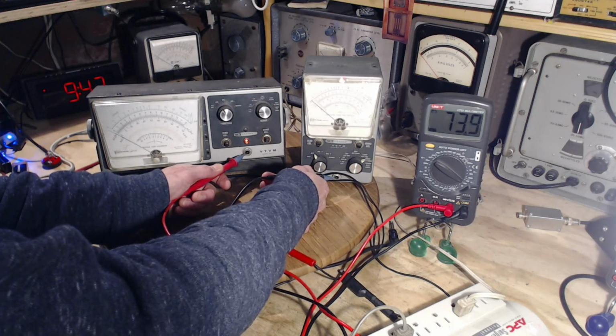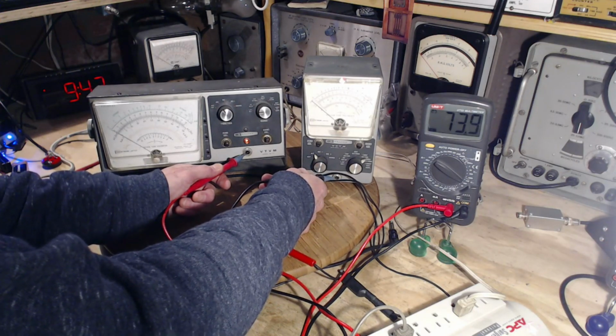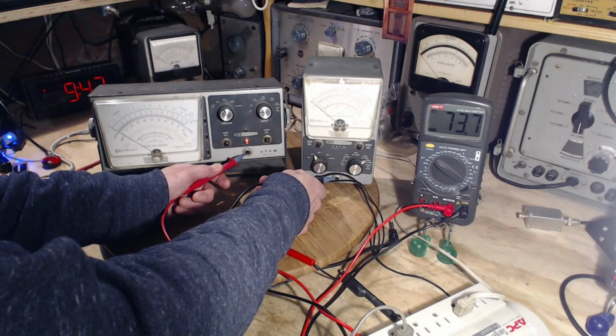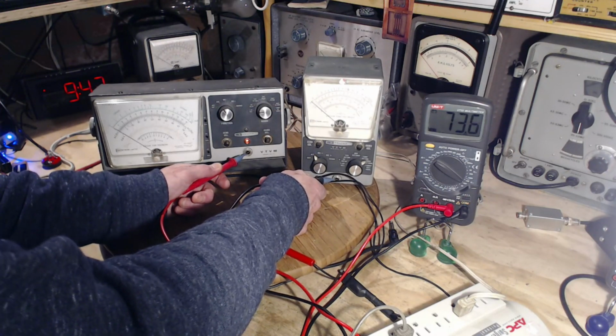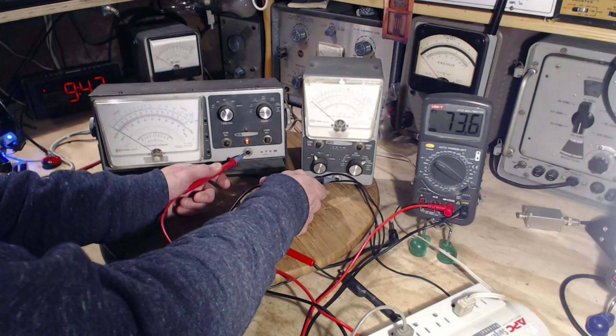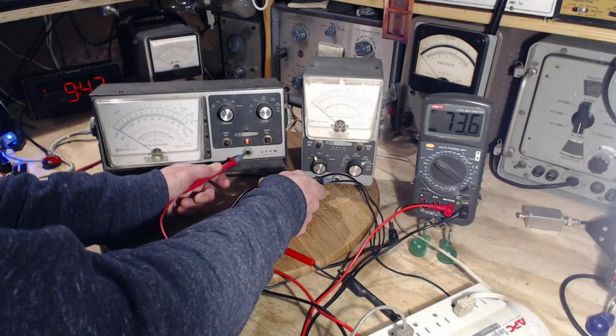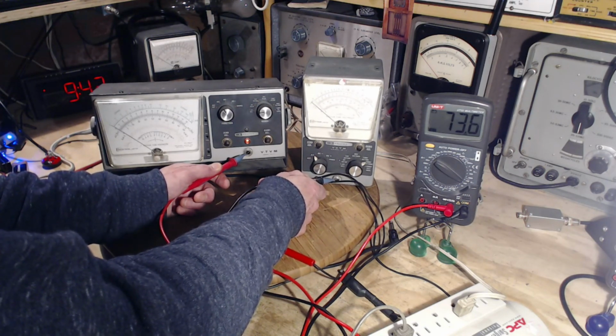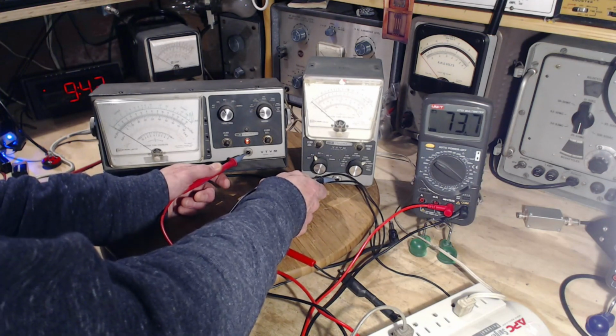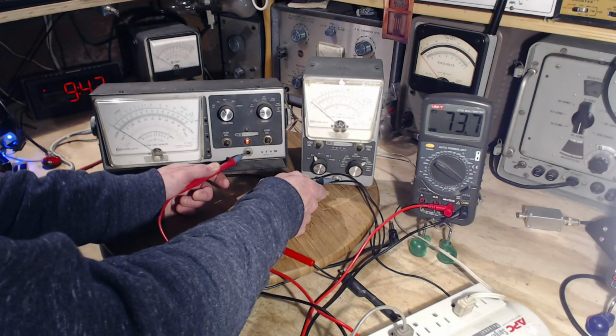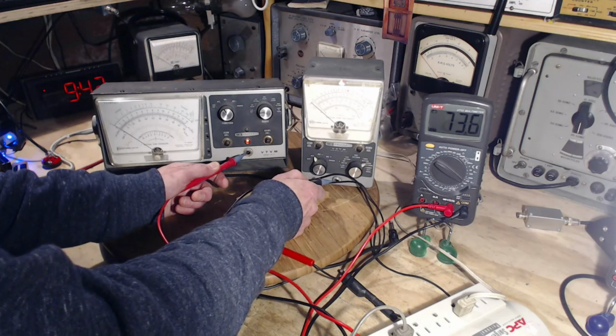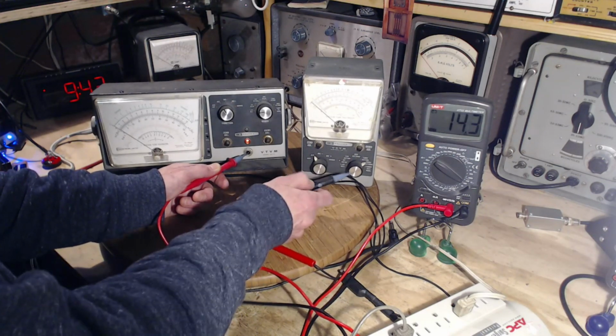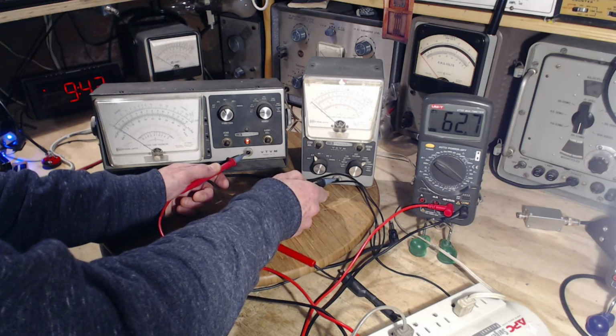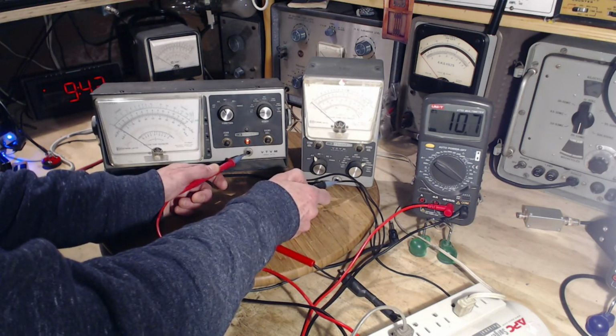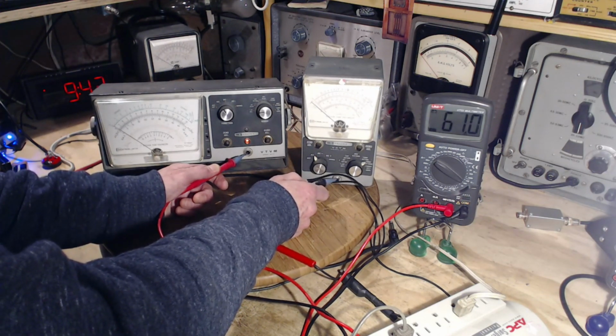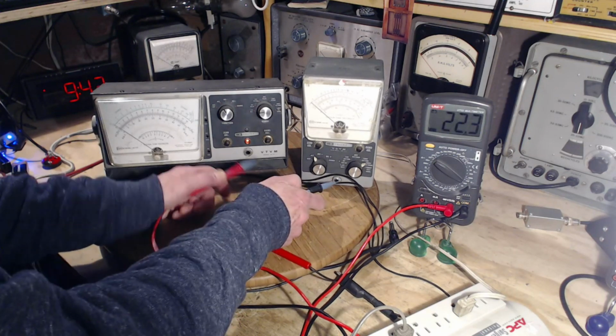Well, it's not 120, but it's still pretty high. So this is the thing about these meters. These little voltages exist. And as I tried to demonstrate yesterday, even if there's no real shock or fire or big short circuit type issue, there can be noise issues from these, just from the slight currents. I have nothing on in the shop that we can hear, but this is probably causing a little bit of electrical noise.